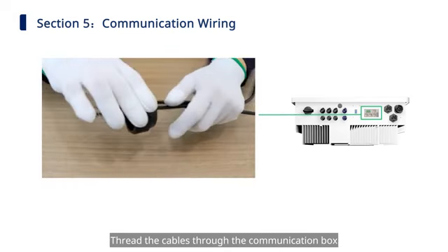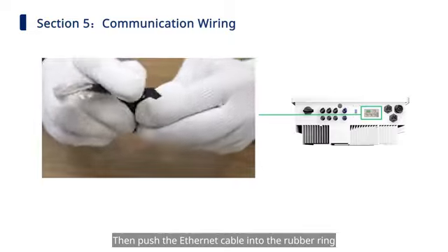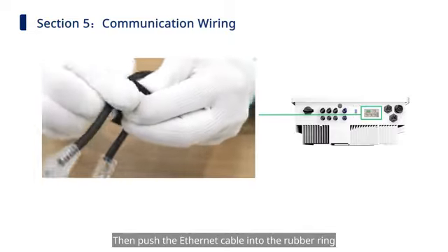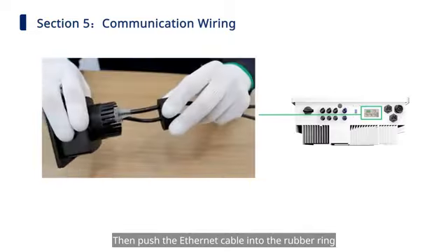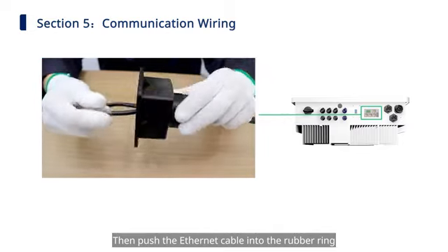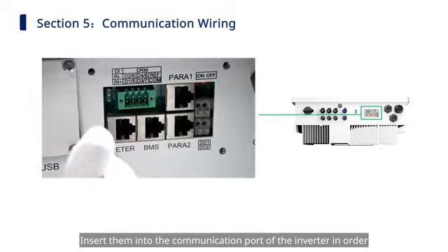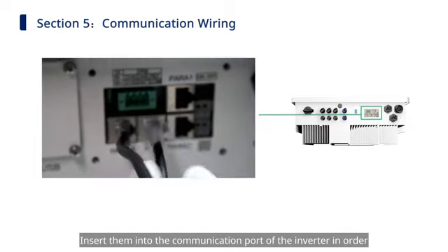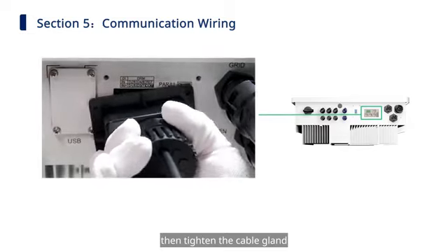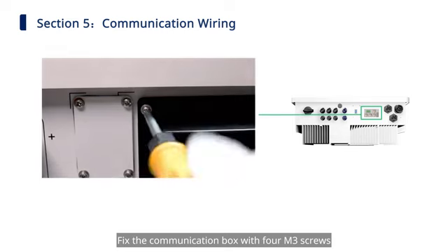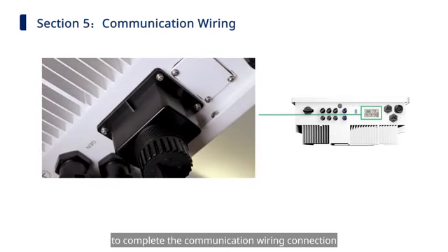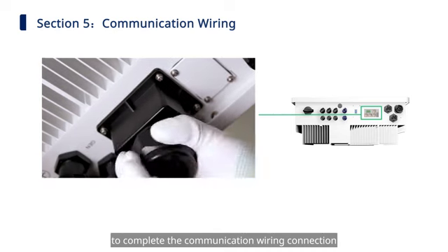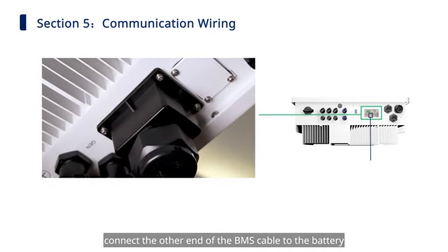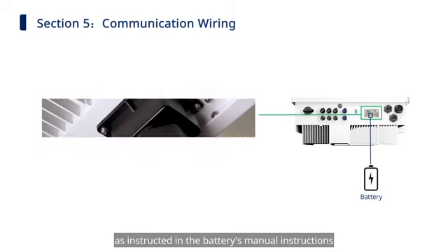Thread the cables through the communication box. Then push the Ethernet cable into the rubber ring. Insert them into the communication port of the inverter in order. Then tighten the cable gland. Fix the communication box with 4 M3 screws to complete the communication wiring connection. Then, connect the other end of the BMS cable to the battery as instructed in the battery's manual instructions.